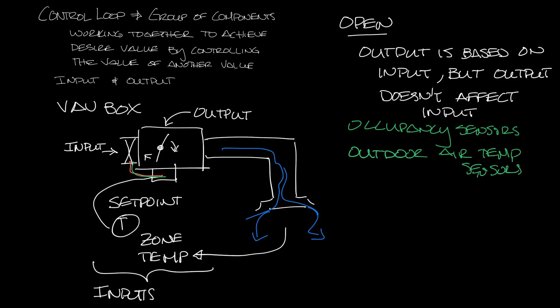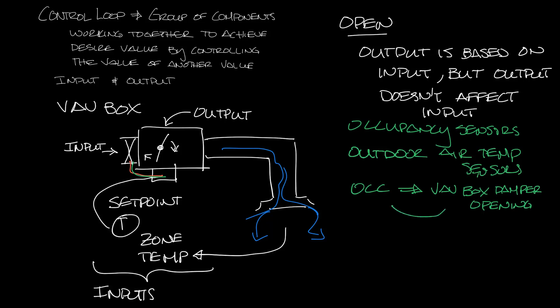So getting an input from an occupancy sensor or an outdoor air temperature sensor could result in the VAV box going into cooling or heating mode which would send an output signal to the damper, but the cooler the space gets does not affect the occupancy sensor or outdoor air temperature. So that's an open loop.